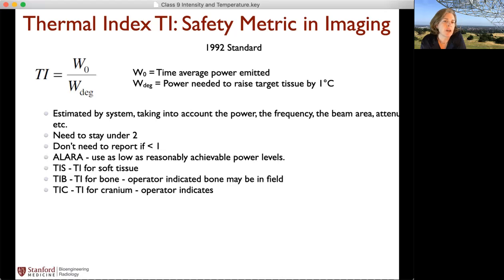For imaging, they defined the thermal index, TI. It's one of the safety metrics, again, 1992 standard. The FDA said that they needed to provide this metric on their ultrasound images. So the TI is defined as the time average power that's emitted into the tissue, divided by the power that's needed to raise it by 1 degree C.